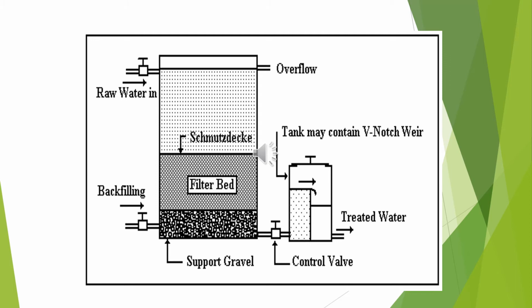Now, below the sand bed, as I told you, there is a layer of support gravel, and from that layer, the water is transferred to the filter bottom through the control valves, and then it goes into the supply where it is disinfected by chlorination.